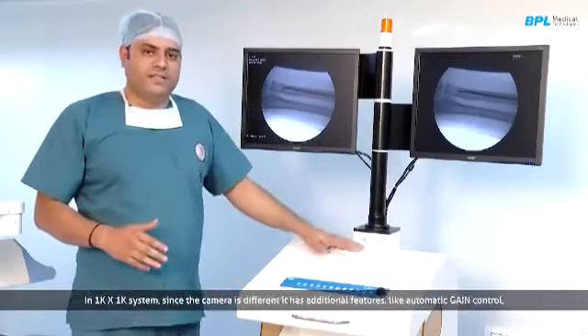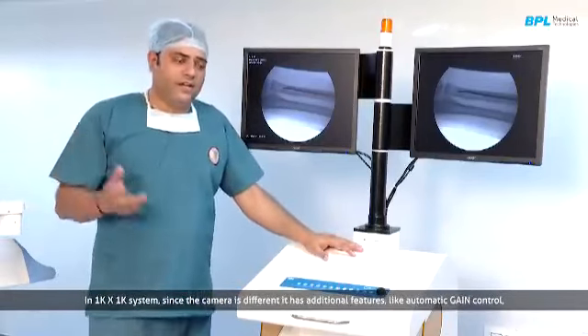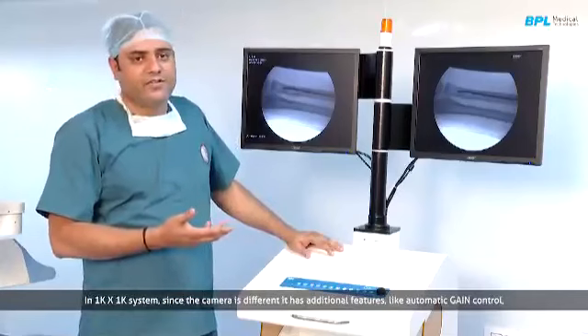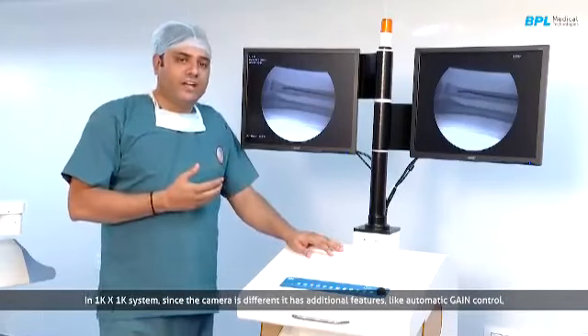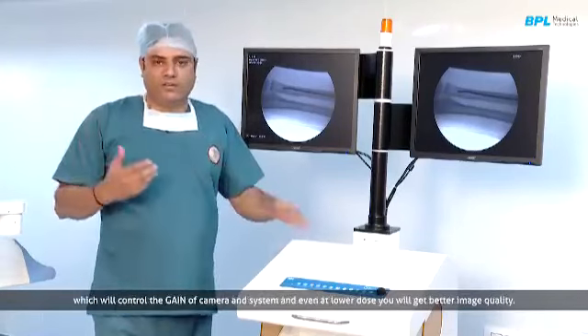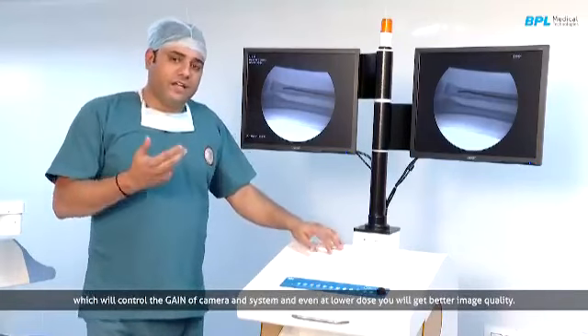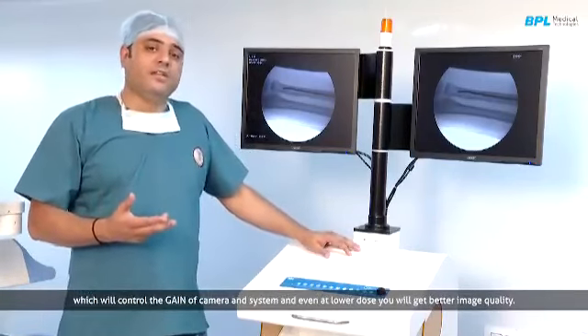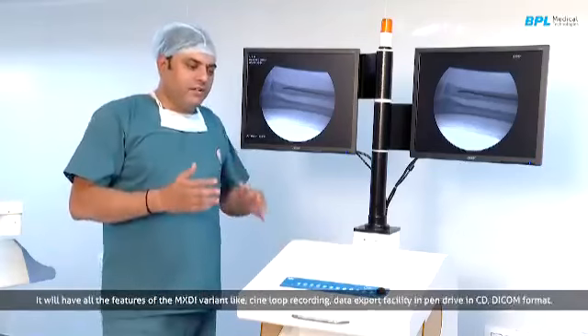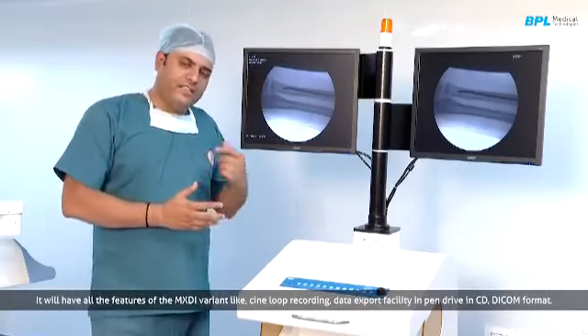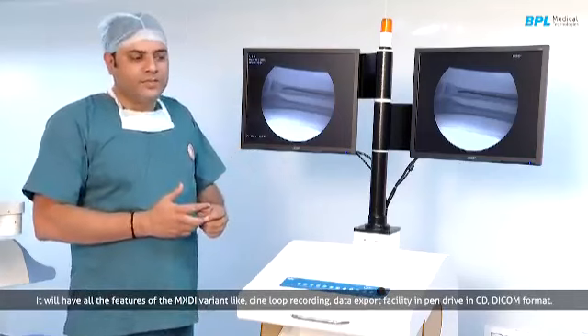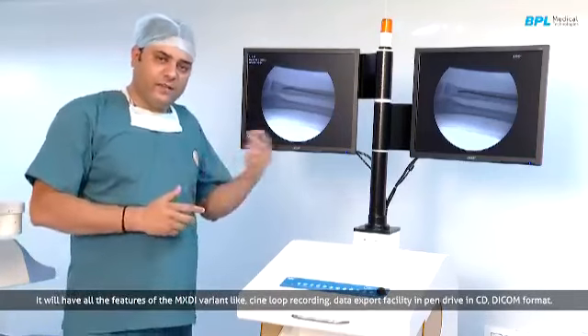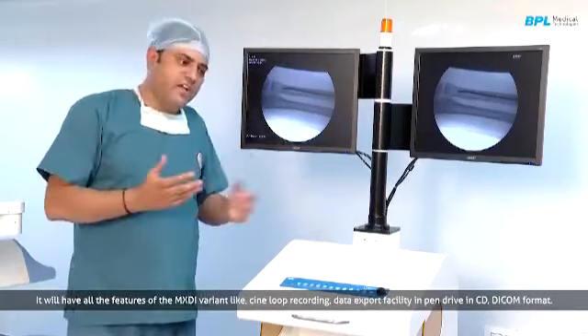In the 1K by 1K system, since the camera is different, it has some further additional features like automatic gain control, which will control the gain of the camera and system, and even at a lesser dose you will get better image quality. It will have all the features of MXDI, like cine loop recording and data export facility on pen drive, on CD, and in DICOM format.